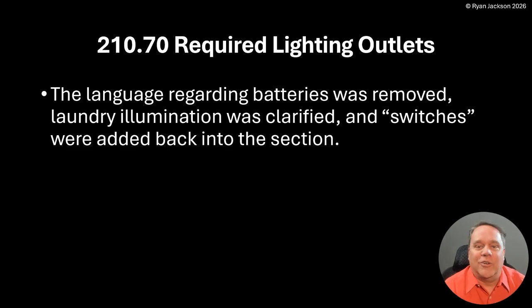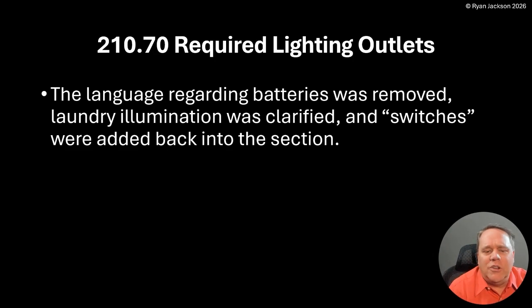So this is the rule that tells you where you have to have a lighting outlet. You've got to have a lighting outlet in the kitchen, in the bathroom, in the bedrooms, and in the laundry area. We added laundry area in the 2023. And as is often the case, when you add a new rule, three years later you have to come back and fix it. So we'll take a look at what we did here in Article 210, branch circuits 210.70 required lighting outlets. The language regarding batteries was removed, laundry illumination was clarified, and switches were added back into the section.